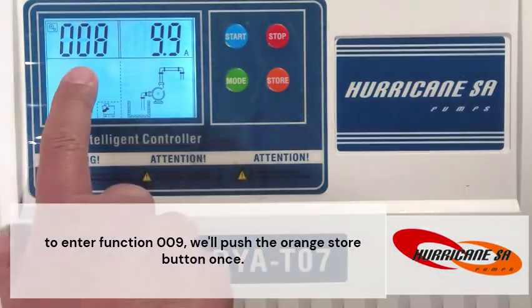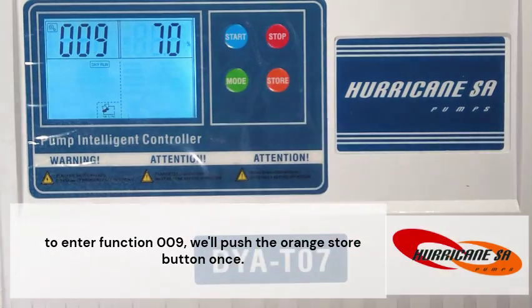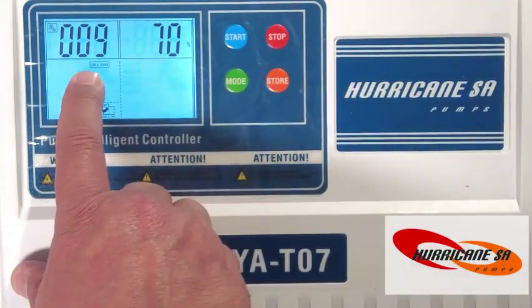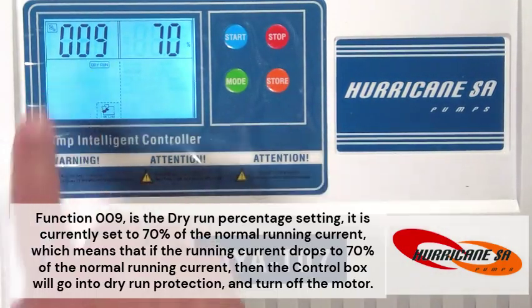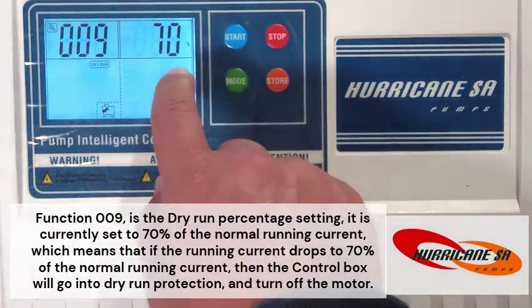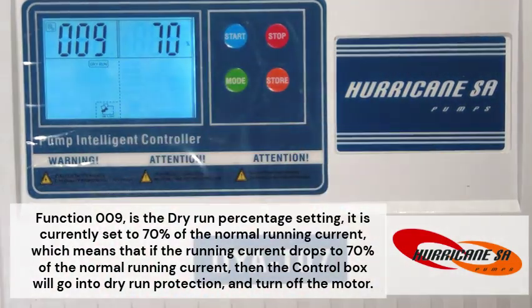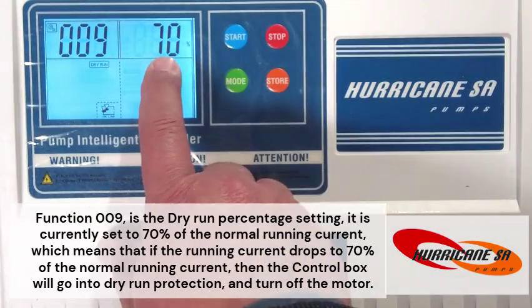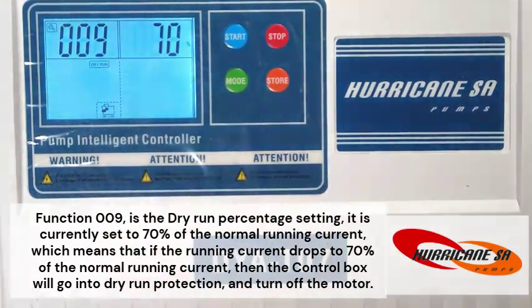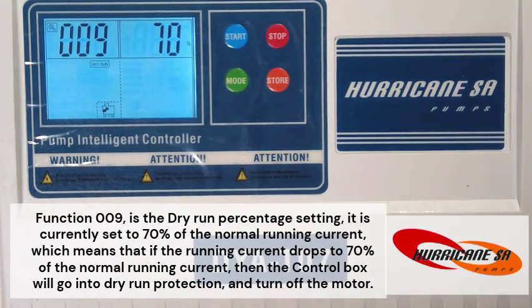To enter function 009, we'll push the orange store button once. Function 009 is the dry run percentage setting. It is currently set to 70% of the normal running current, which means that if the running current drops to 70% of the normal running current, then the control box will go into dry run protection and turn off the motor.